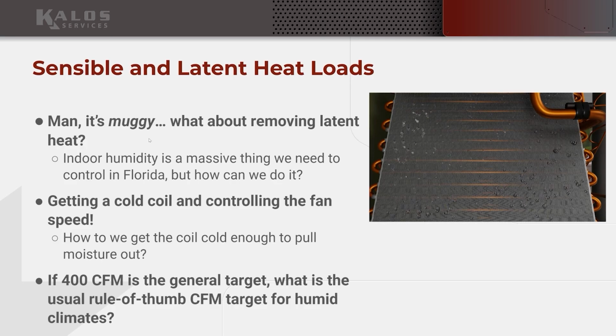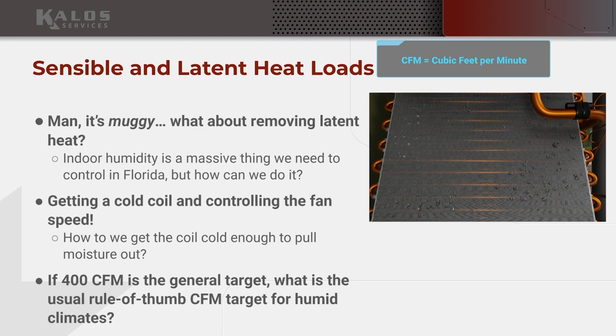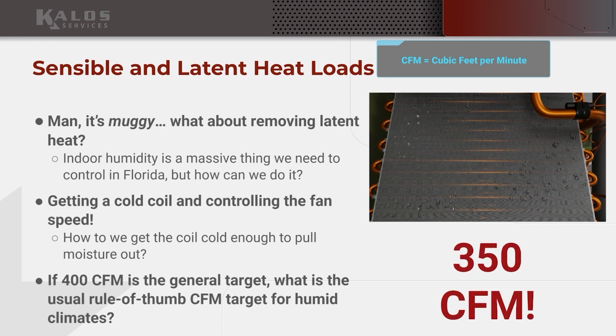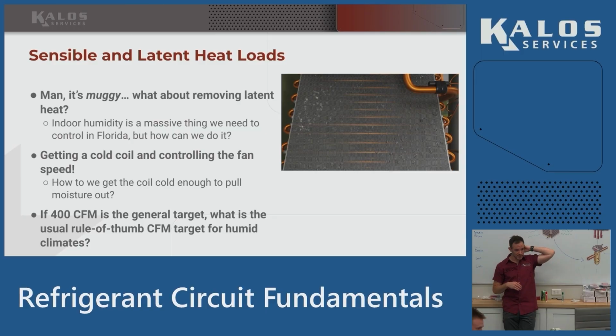In most parts of the country, they're usually trying to hit 400 CFM, which is cubic feet per minute, how much volume of air we're moving across. In Florida, we actually go lower. Our target CFM for this market is 350. Per ton? Yeah, 350 per ton, exactly. So for a 2-ton system, I would want a CFM of 700. For a 3-ton, it'd be 1050. Most of the time the manual will give it to you either in CFM per ton, or just the flat number, and you can calculate it based on the tonnage of your system. The reason we want it lower, though, is because of this.